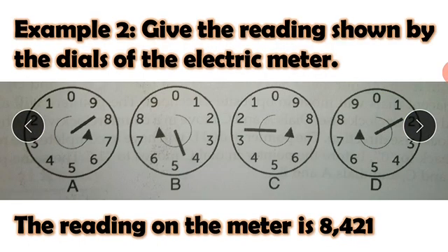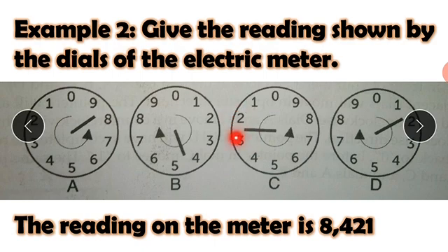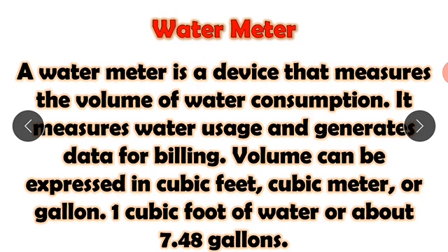Now let's give the reading shown on the dials of the electric meter. Starting with A: between eight and nine, that is eight. Between four and five, that is four. Between two and three, that is two. Between one and two, that is one. So the reading is 8,421. Now let's proceed to water meters.